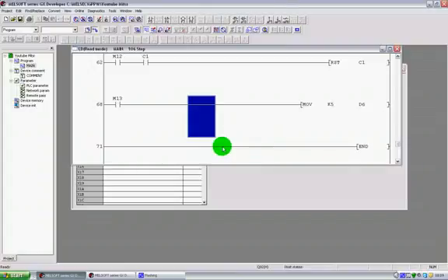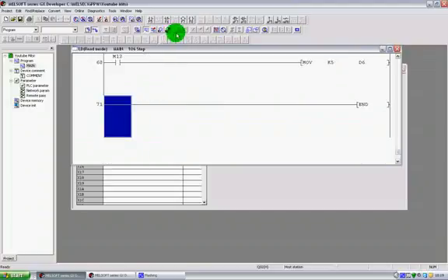Again, you've got to be a little bit careful with these values and these moves, especially if you're using contacts like this, because you may be making this line true constantly. Now if this happens to be another data register, then if one value keeps changing, then it will change the other one. So sometimes you may only want to put the value in on a pulse.